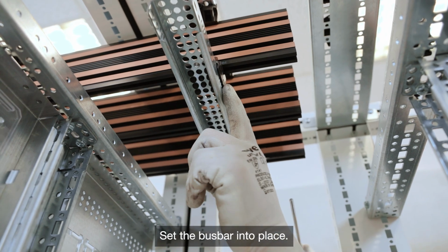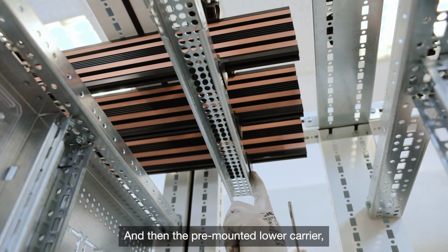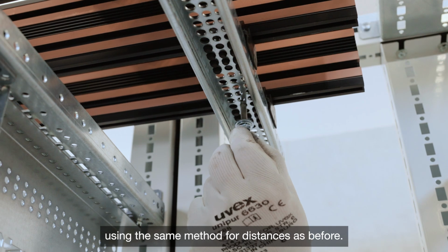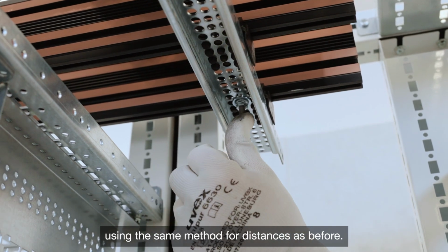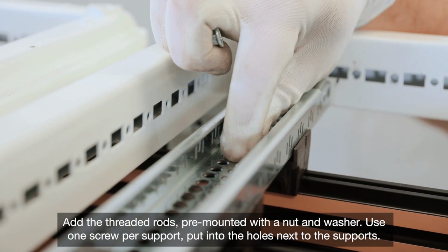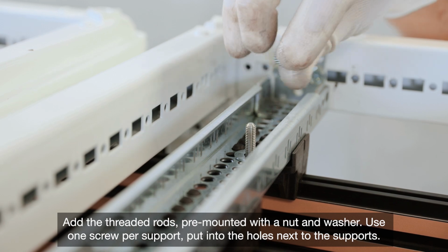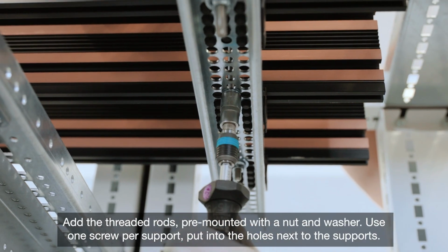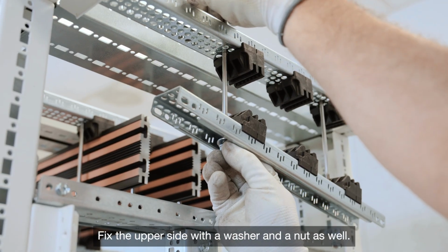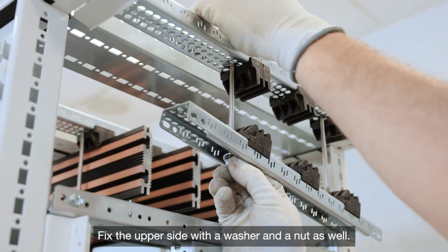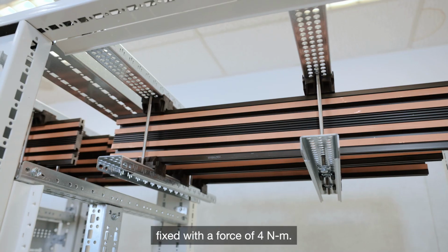Set the busbar into place. And then the pre-mounted lower carrier. Using the same method for distances as before. Add the threaded rods, pre-mounted with a nut and washer. Use 1 screw per support. Put into the holes next to the supports. Fix the upper side with a washer and a nut as well, fixed with a force of 4 Nm.